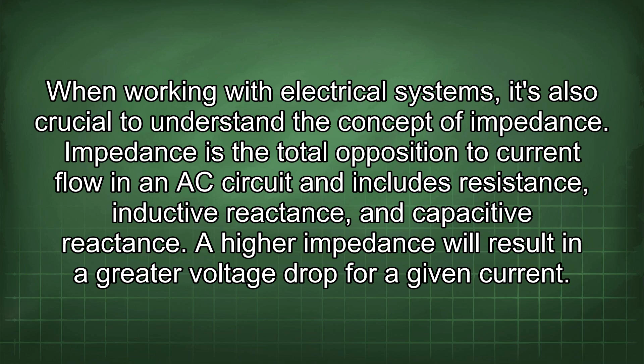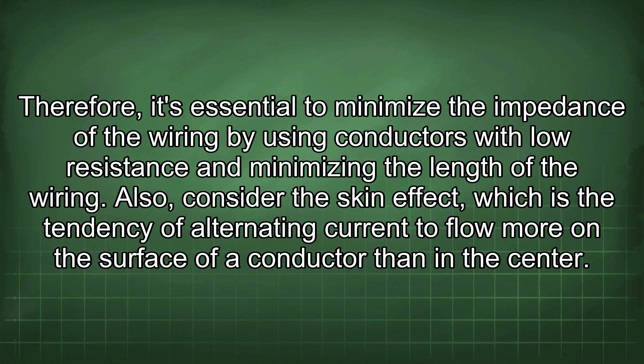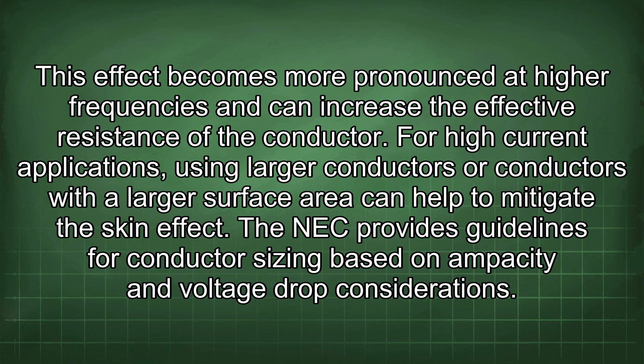Also, consider the skin effect, which is the tendency of alternating current to flow more on the surface of a conductor than in the center. This effect becomes more pronounced at higher frequencies and can increase the effective resistance of the conductor. For high current applications, using larger conductors or conductors with a larger surface area can help to mitigate the skin effect. The NEC provides guidelines for conductor sizing based on ampacity and voltage drop considerations.